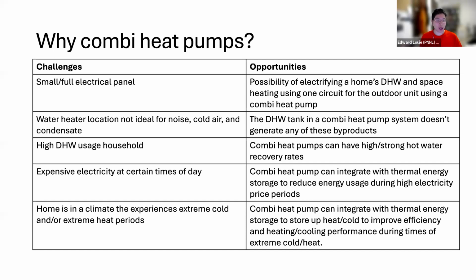and then save electricity during the hours when electricity is very expensive. And then, as we know, heat pumps work well, but during very, very cold, extreme hours of the day, in the coldest days of winter, or the hottest hours in the summer, heat pumps really do still struggle. And so with thermal energy storage, you could store up heat or cool in tanks during more mild hours of the day, and then use that stored heat or cool during the peak hours and save energy and gain cooling or heating performance as a result. So those are some of the really cool value propositions, reasons why combi heat pumps are awesome. Next slide.